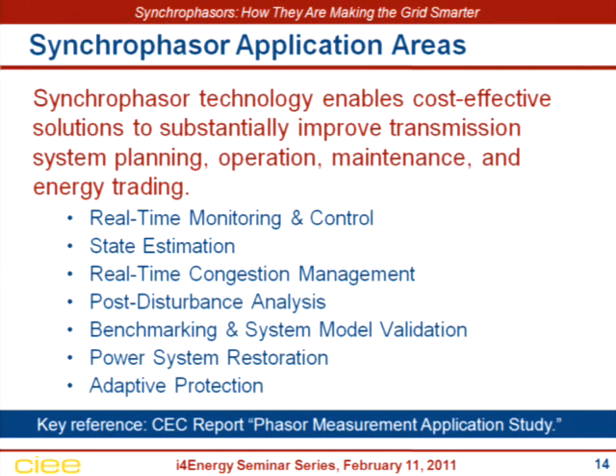There's also benchmarking and system model validation. An awful lot of what the power industry currently depends on for doing system analysis is based on models. They model the system in the computer, run what-if contingencies, test the limits, and come up with operating limits, constraints and guidelines for how to operate the system. But that's only as good as your models are. If your models are no good, or the data is inaccurate, you'll get erroneous results. So synchrophasor data is just much better garbage in to get much better garbage out, so to speak.